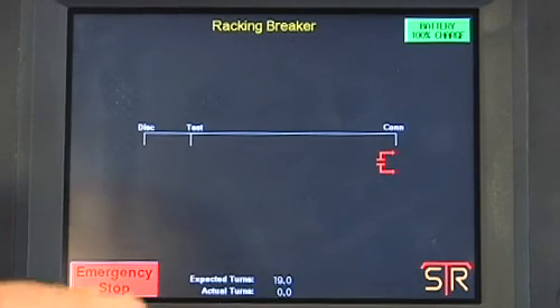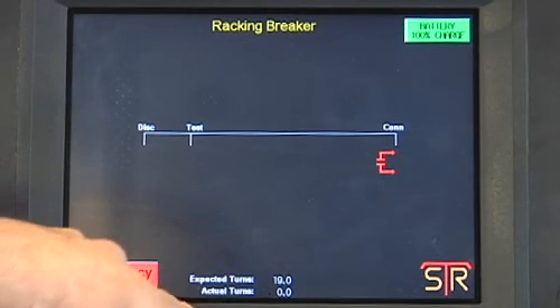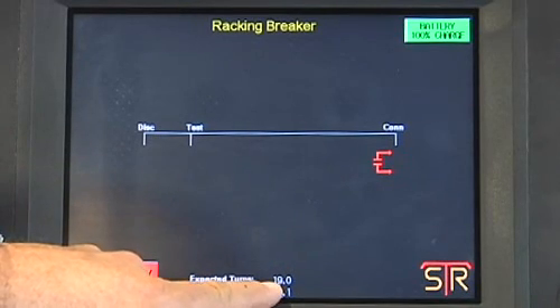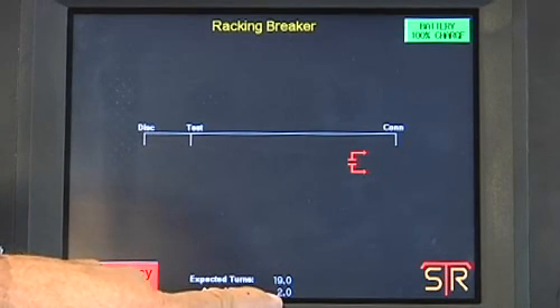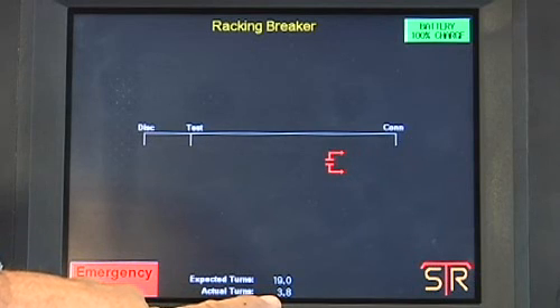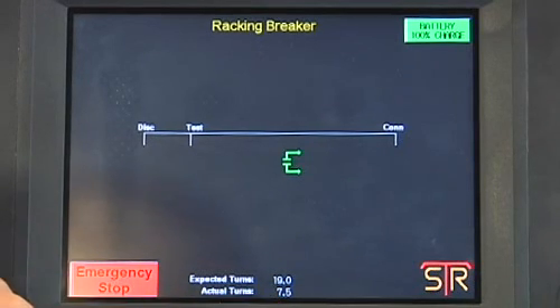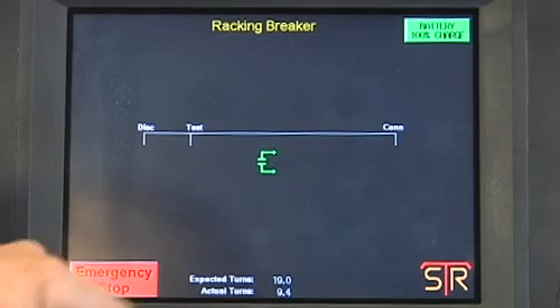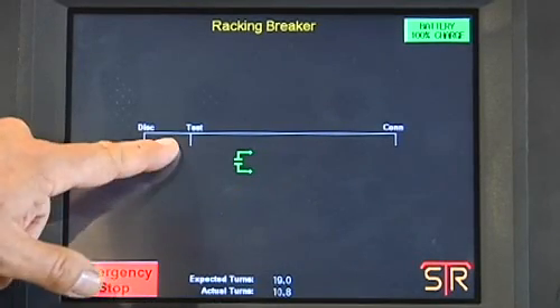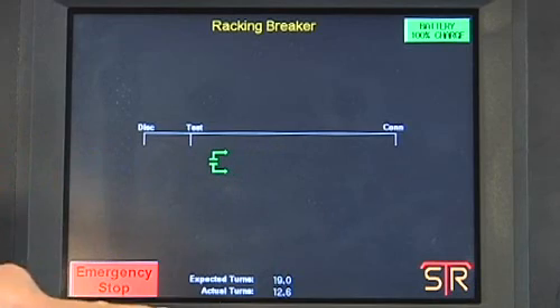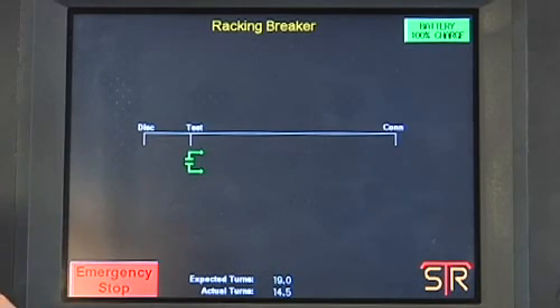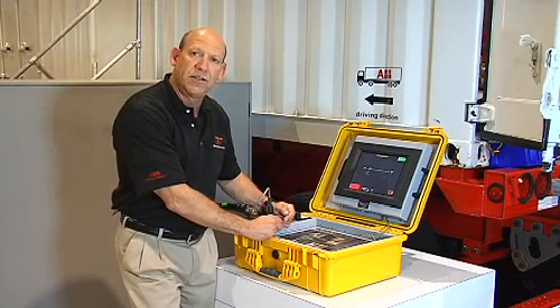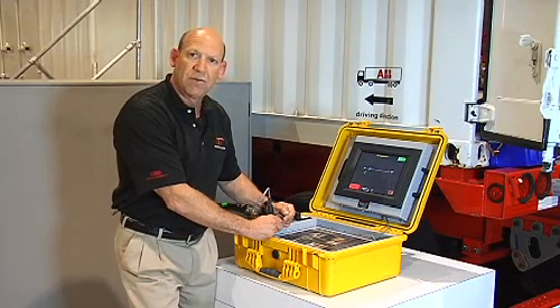It will engage the tool, wait for the connection to be made, lift the positive interlock, and start to rack the circuit breaker. We will notice that we start from the connect position. It will start traveling outward, giving us our expected turn count. In this case, for this application, it's 19 turns and an actual dynamic logging of turns received. It'll pass the test position automatically, releasing the interlock and then slowing down into the disconnect position.